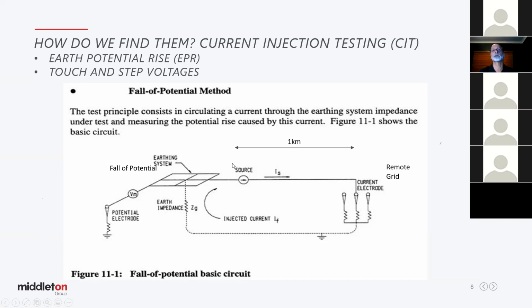And what we have here, using Ohm's law, is a current source. We're going to move that current around the circuit. That includes the earthing system and the resistance of the grid of that earthing system. As we know from Ohm's law, if we push a current through a resistance, it will generate a voltage. So this is simulated fault current. We only push 5 or 10 amps around, as opposed to perhaps the 10,000 amps that will flow during an earth fault. So we're only going to create voltages at this substation under test about 1/1000th, in this case, of the actual voltages that will occur during an earth fault.